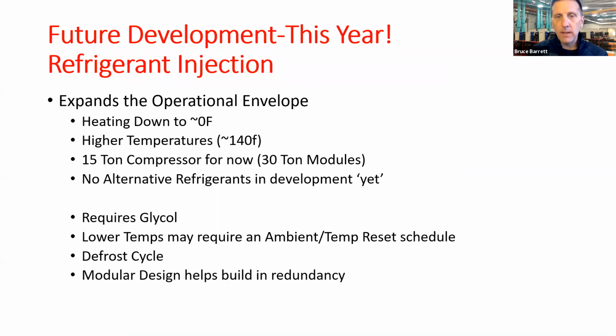There still is going to be reset schedules involved as we travel down to near 0 ambient. There is also a defrost cycle. You can frost your coil. You need to warm it up. So you need redundant modules to carry the load while you're doing defrost in that dormant thawing out cycle for the module. That's where the modular design comes into play. You can plan for that defrost cycle by adding a redundant module.